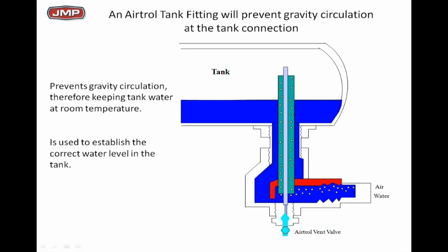In other words, you fill your system up with water. The tank is sitting at 0 psig when you start it off, and you start adding water in it, so you've got an air cushion, but that air cushion is going to be under pressure. It's going to compress somewhat, and you don't have a tank that's 100% acceptance volume. That's why bladder tanks, properly charged, can physically be smaller. One other quick comment on this: this Airtrol tank fitting needs to be above the air separator so we can have the air moving back and forth by gravity, by just rising air.